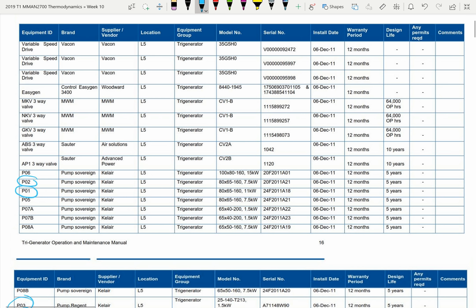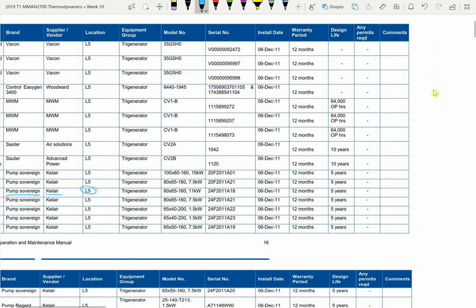Let's track pump 1 through the system. Pump 1 is called a pump sovereign, sold to us by Kelair. The model number is 80x65-160 running at 11 kilowatts — this is important information. Every pump produced will have a unique serial number. I'd suggest this pump might have been produced in 2011 based on that serial number, so it was built sometime during 2011.